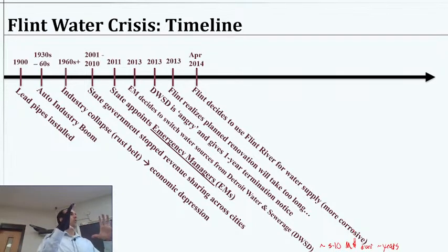What we want is, over the course of 100 years, maybe a pipe's going to get so coated with the mineral deposits that eventually we'd have to dig that up and replace it. That's a much better outcome than having it break. So by design, we normally have this anti-corrosion, in a sense, this precipitation type of dynamic for our piping systems.